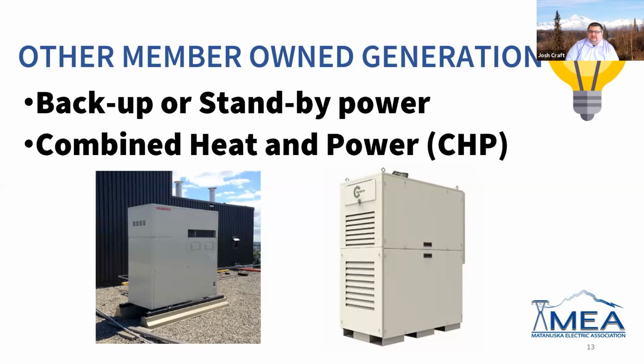The issue we run into is that they're burning fossil fuels, which are not renewable and therefore not eligible under the MEA QF1 or the net metering program. So you would basically be generating your own electricity, but anything you generated that went onto the grid, you wouldn't get credit for. However, you can still be hooked to the grid - we just have special safety requirements in place to make sure it can't hurt our personnel.